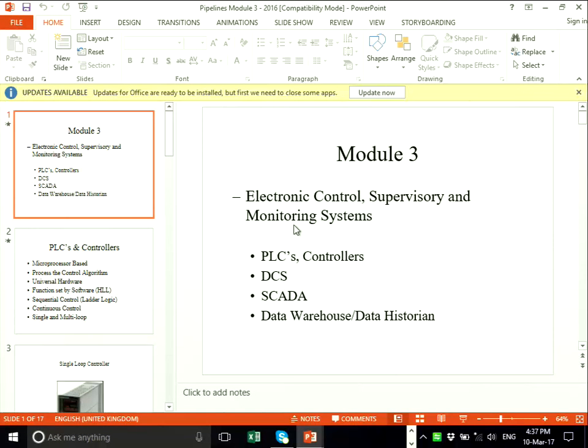But if the telemetry unit on site breaks, then you've got to send somebody out to investigate, and you've probably lost that data in the meantime. But on a lot of systems, you'll have other stations nearby, so you'll know if pressures are going wrong. Unless you're on a single feed sole supply, and the UK system is quite integrated and looped. It might be a bit different on a transit pipeline system, where you're going point to point to point to point, and maybe they're quite a distance apart.